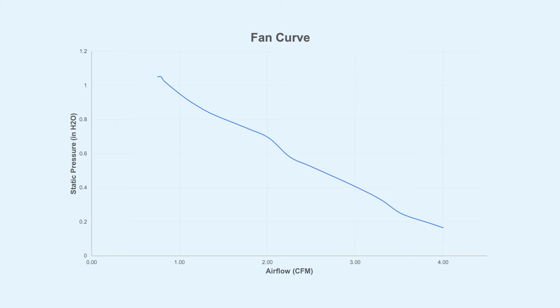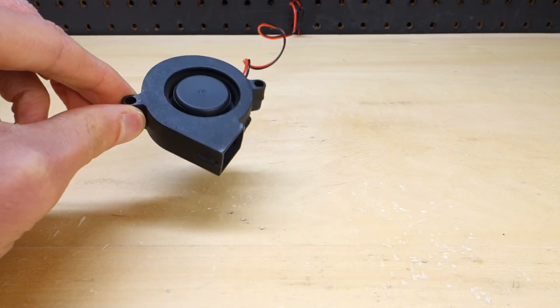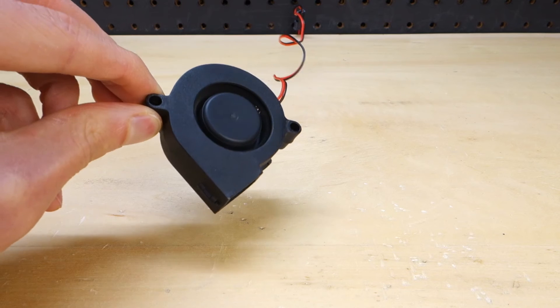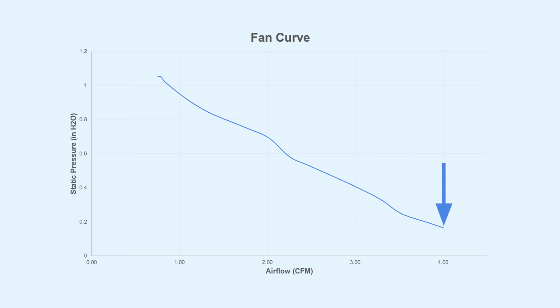But where do we begin? Let's begin with the point on the very right. This is pretty much where the fan is basically fully open. There's very little resistance to the airflow and it's pretty much the most air the fan will blow. So basically this blower fan can blow 4 CFM with just under 0.2 inches of water of static pressure, which basically stands for how much resistance there is to airflow.